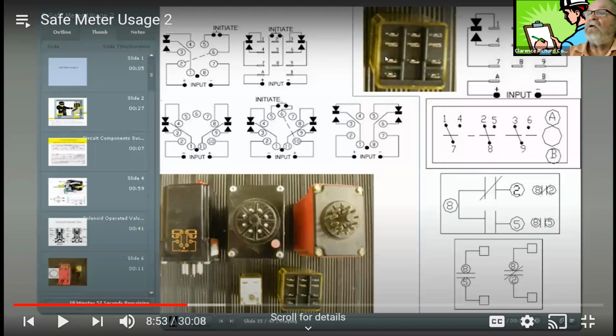This here looks at the bottom part of it. This is your relay. If you look at these 2 right here, this goes to your coil on your electromagnet. That's A and B. All you've got to do is put 120 volts on one side and 0 on the other. Or if it's DC, you put common or 12 volts or 24 volts, whatever that relay coil is. You can get relay coils for DC and AC. You can get some coils that will energize on 480 volts versus 240 or 120. It's kind of like mix and match depending on what your power supply is.